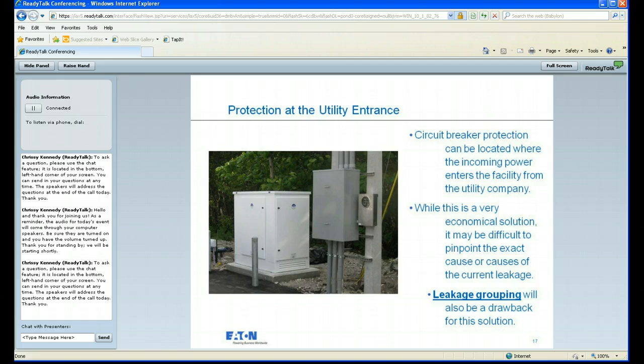Basically, you put this right where the incoming power is entering the facility. It's a very economical solution, depending on the size of the service you're looking to control, because you're only buying one piece of equipment. It's just a circuit breaker that's going to have the ground fault protection in it. With it being at the head of all of the electrical circuits that filter from your distribution panels down to your boats, it's going to be very difficult to pinpoint the exact cause or causes of the leakage unless you go pretty much boat by boat turning on circuit breakers to figure out what boat or boats are causing that main circuit breaker to trip.